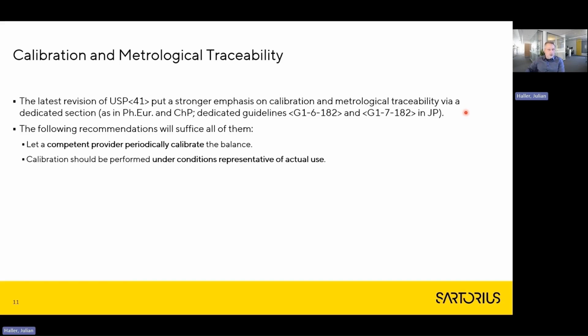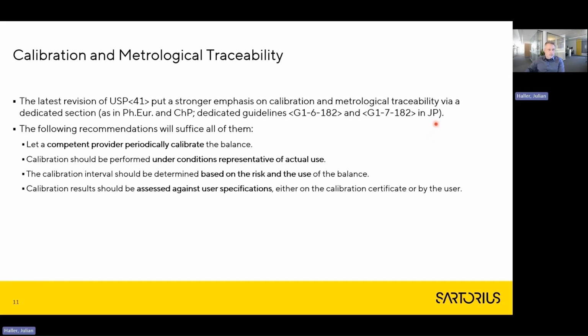The calibration should be performed under conditions representative of the actual use, so there should be no efforts to provide especially good conditions just for the calibration. The calibration interval should be determined based on the risk and the use of the balance. Calibration results should be assessed against user specifications, and this should be done either by the user with the respective proper documentation, or, which is a bit easier for the user, directly by the calibration laboratory on the respective calibration certificate.